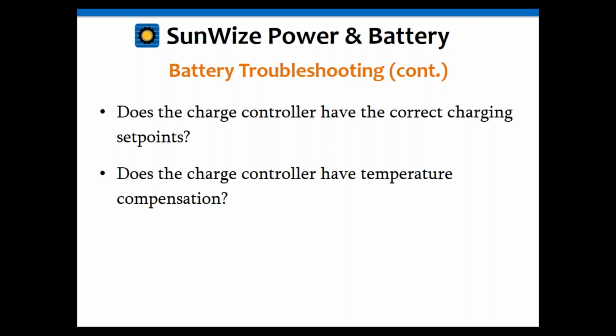Because they were reading a voltage that was off by quite a bit. It was reading too high, and the batteries weren't getting fully charged. After they adjusted for temperature, the batteries were being charged by almost a whole volt less than they should have been, because it thought everything was too hot. So having proper temperature compensation and measuring that battery temperature correctly is very important.